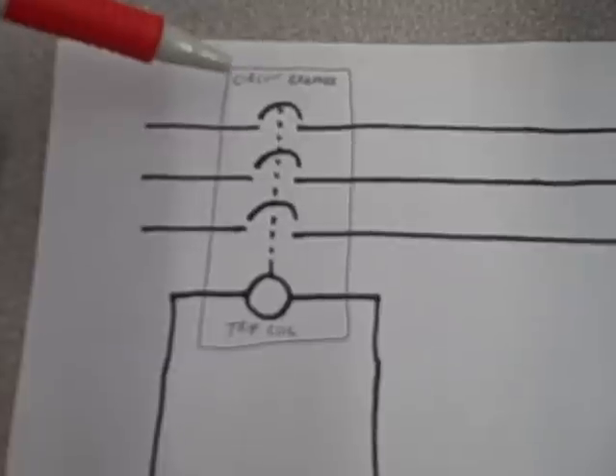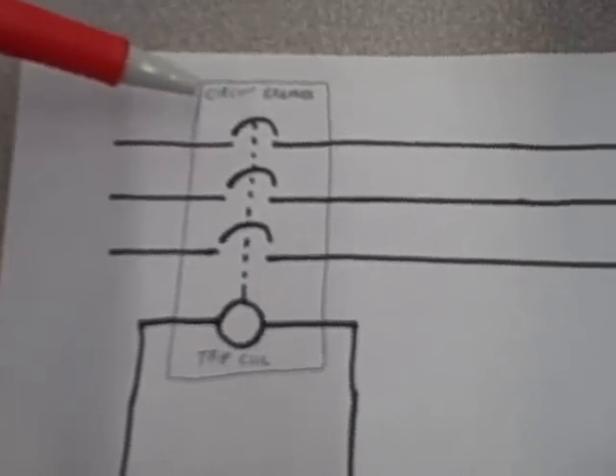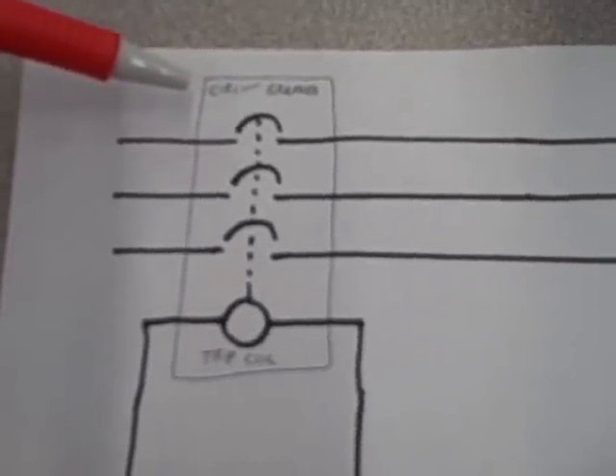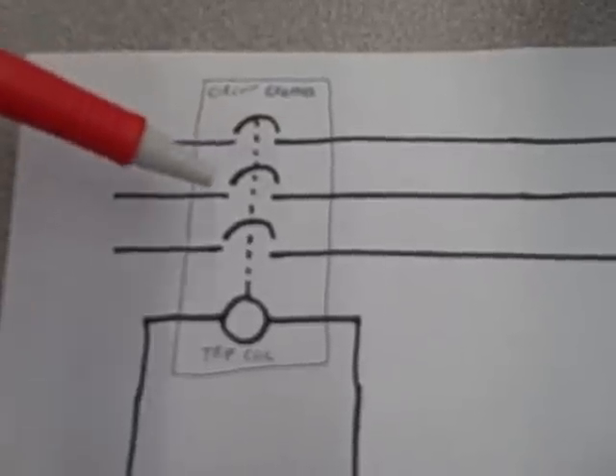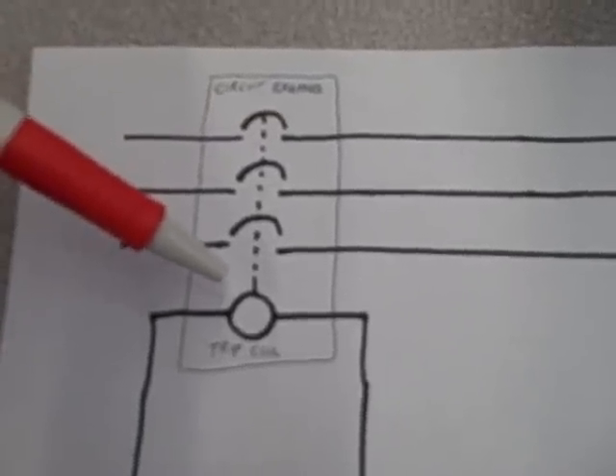So in order for this breaker to break the circuit automatically and to protect it from overcurrent conditions or any other dangerous conditions, we have to have some other device, some external device, send a trip signal to the breaker.